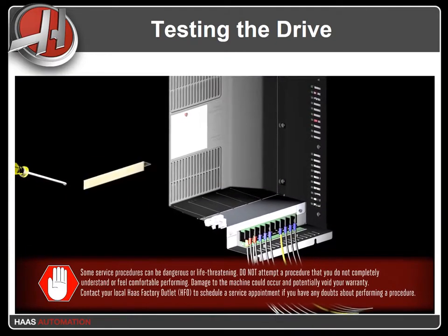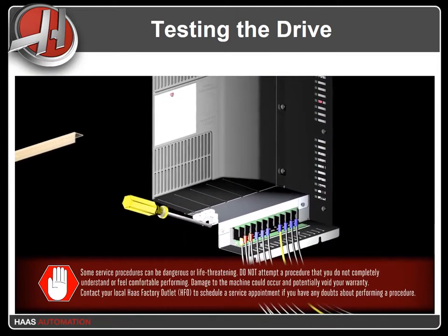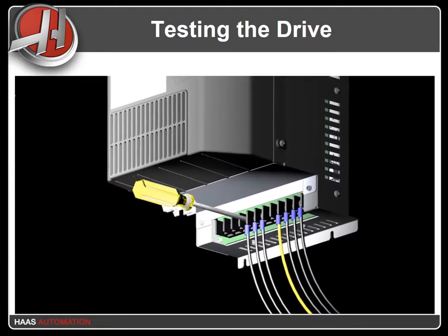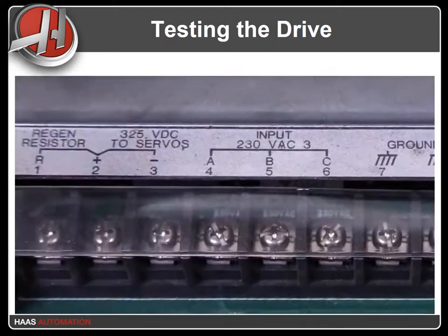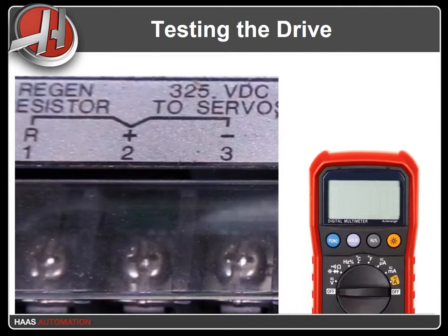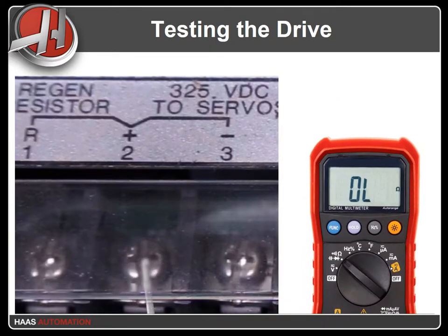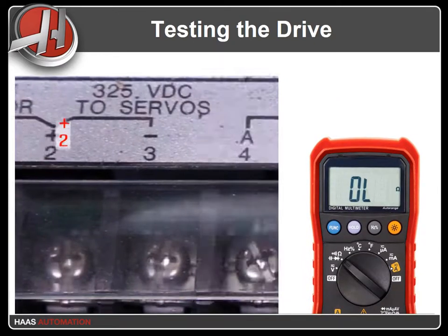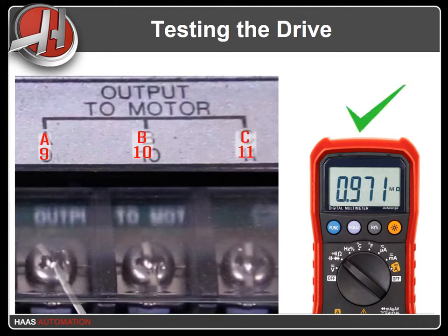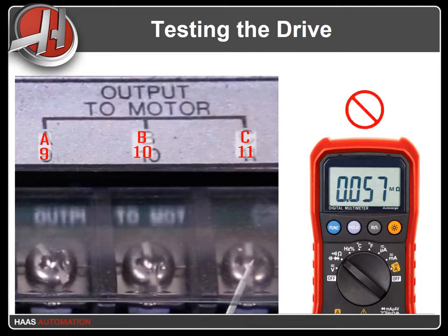Once you're certain that there is no voltage in the vector drive, label and remove the leads from the DC bus. In our tests, we want to make sure we are only measuring resistance through the vector drive itself. First, check the output on the positive side of the DC bus. Set your multimeter to resistance test mode and put the black lead on terminal 2, labeled with a plus sign. Use the red lead to measure the resistance to motor terminals 9, 10, and 11, labeled A, B, and C. The meter should show high resistance readings, typically in the range of kilo or mega ohms. If your meter reads very low resistance, the vector drive is damaged.